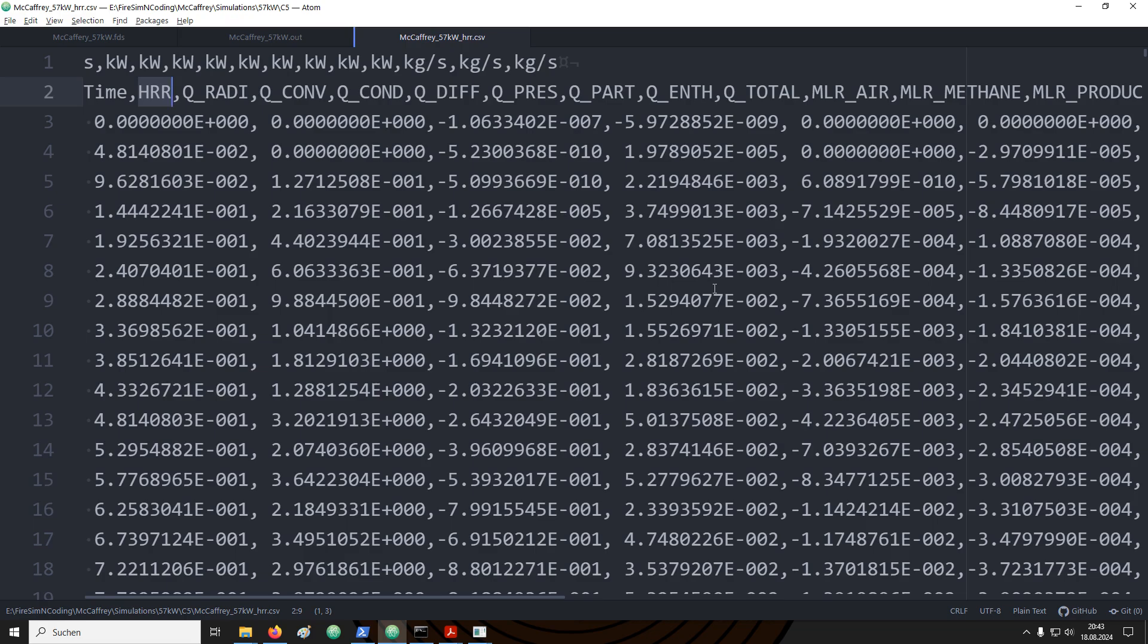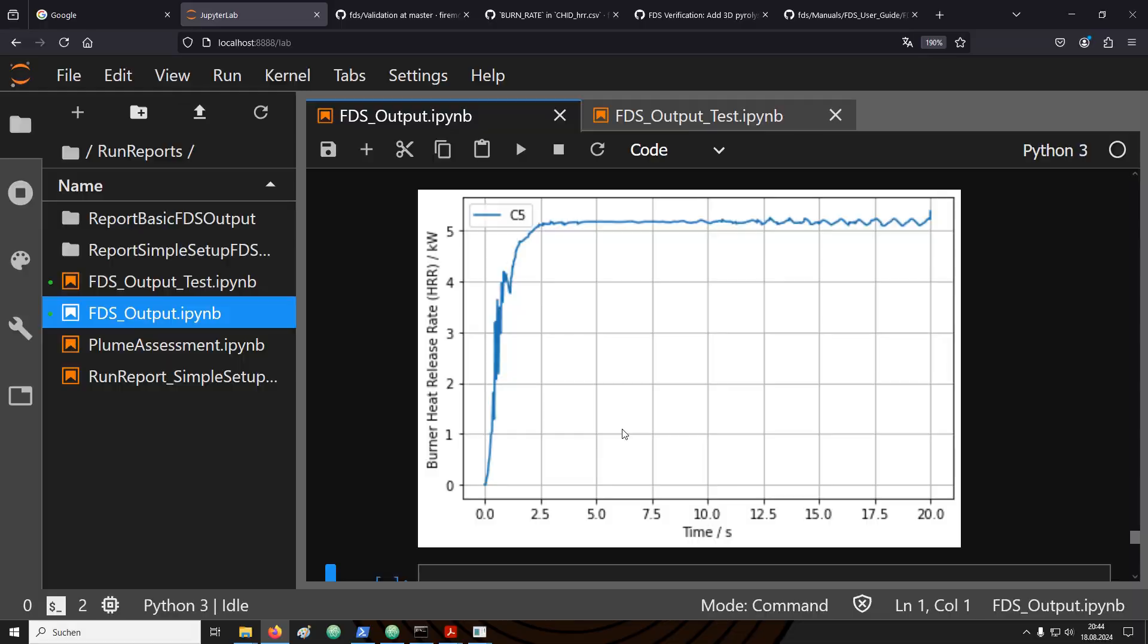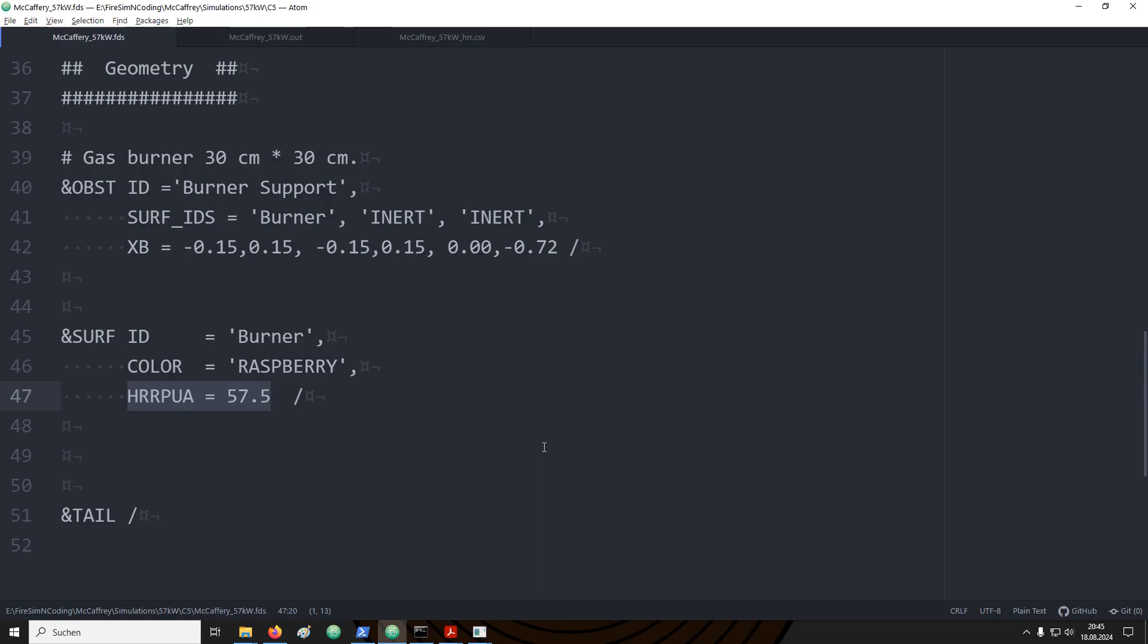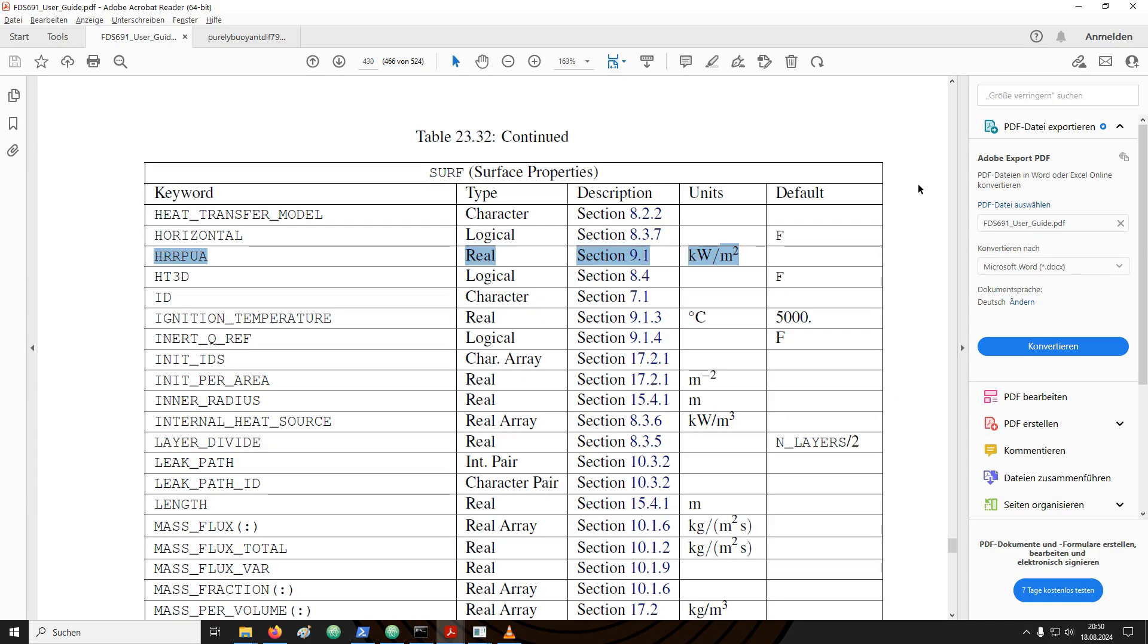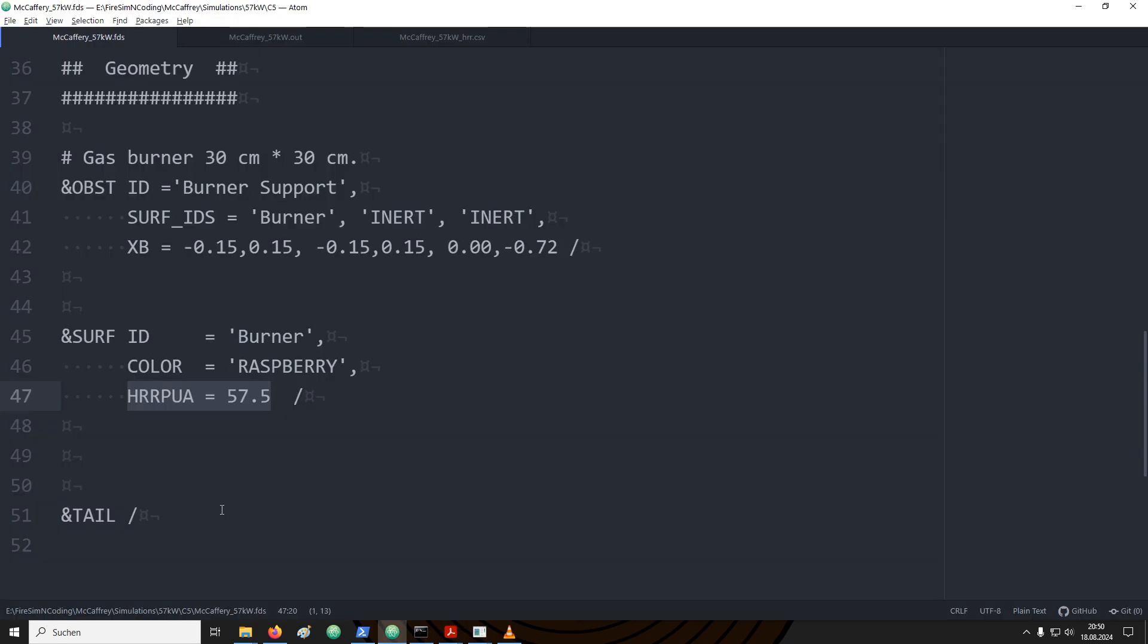Let's have a look at the gas burner now. According to the experiment, we wanted to have a gas burner that has a constant heat release rate of 57.5 kW per square meter. To figure out where we are at with the simulation, we can simply plot the heat release rate against time. In this plot, we will see that FDS will ramp up the heat release rate in the beginning. After this initial ramp-up, it stays fairly constant. This is the result of us providing the heat release rate per unit area to the surface. We could change this gas flow with a ramp. If you are interested in that, you can have a look in the user guide for the ramp Q. We will also discuss this later. The HRRPUA parameter is a convenience function within FDS. It allows us to easily define a mass flux of some combustible gas over a certain surface area. The value for this parameter is provided in kW per square meter.